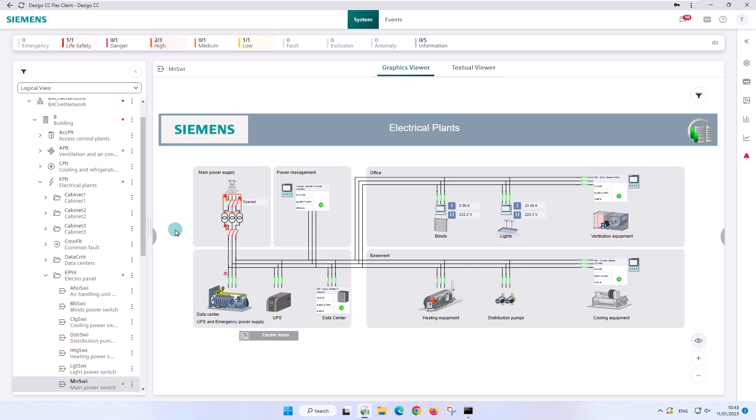Propagation is based on the parent-child-grandchild model. Each object in the system can have one or more parent objects and one or more child objects. Each child in the system can simultaneously propagate multiple active common status properties to a parent, such as alarm, fault, or technical exclusion.